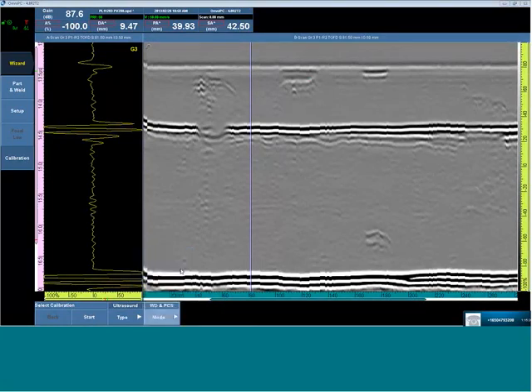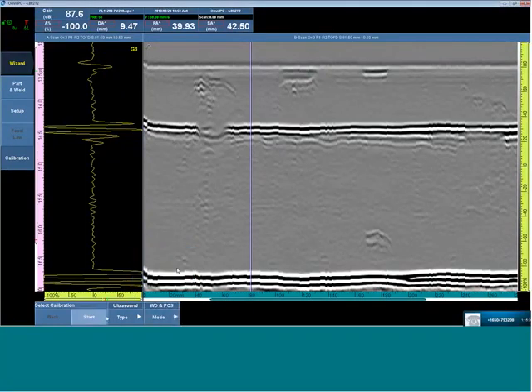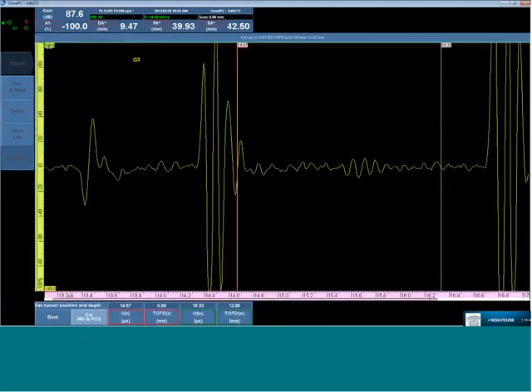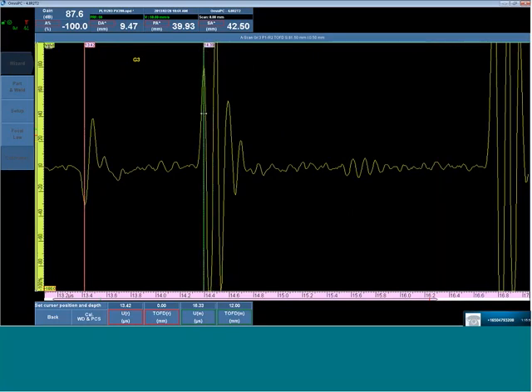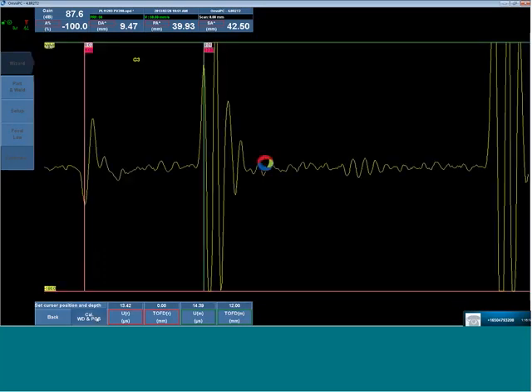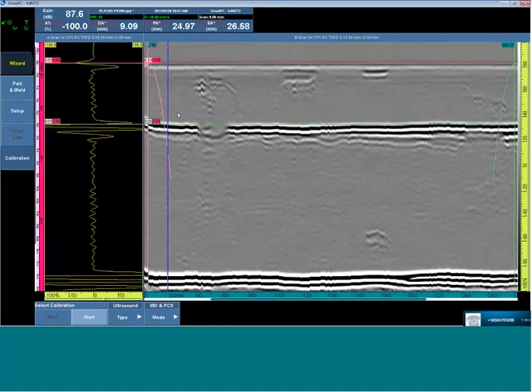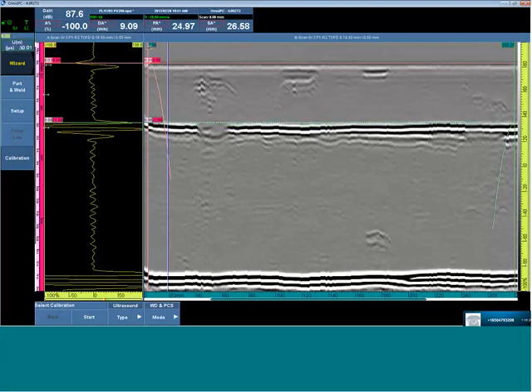Now we calibrate wedge delay and PCS — a new feature in the 4.0 version of the software. We take a representative A-scan, enter the thickness defaulted from the component, identify the lateral wave first negative peak and the back wall first positive peak. This converts microseconds to millimeters: zero representing the part surface and 12 millimeters representing the part back wall. We select calibrate, verify that velocity and wedge delay look normal and PCS has been entered, select accept, and now zero and 12 mm are linear inside our area of interest.